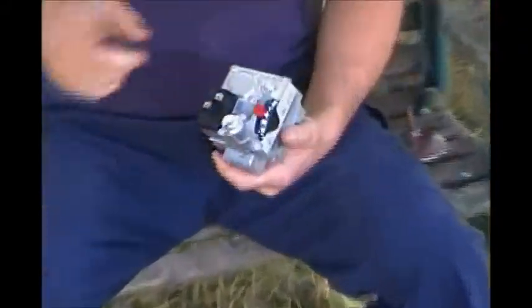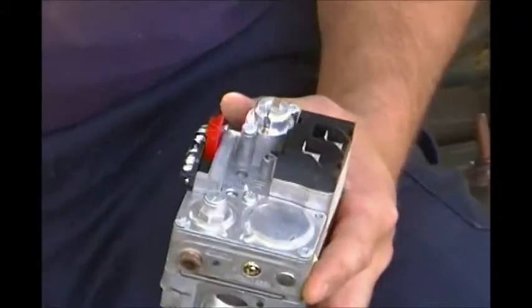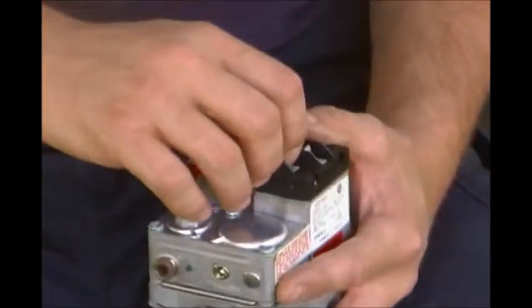On the top here is where a thermocouple would go - it would screw in here, go down, follow your tubing that comes out over here down to the burner. When the thermocouple is nice and warm and hot it will send a signal back saying there is a flame, so we can have main burner. As long as the high limit and the safety controls are all made - they're normally closed, open when there's a fault - it will take the 24 volt and your main gas will come on.